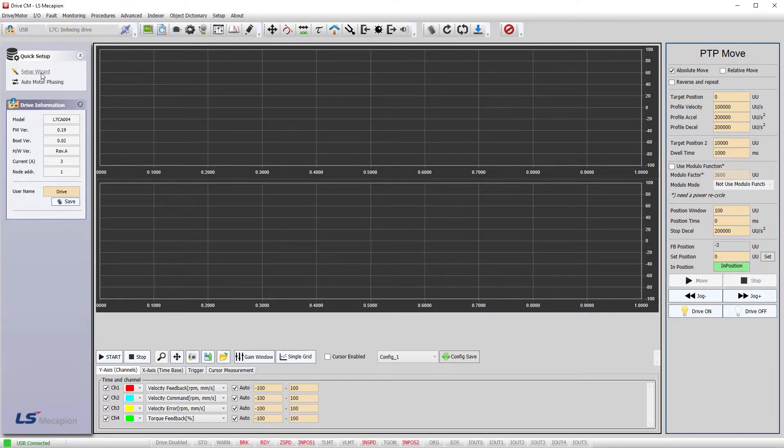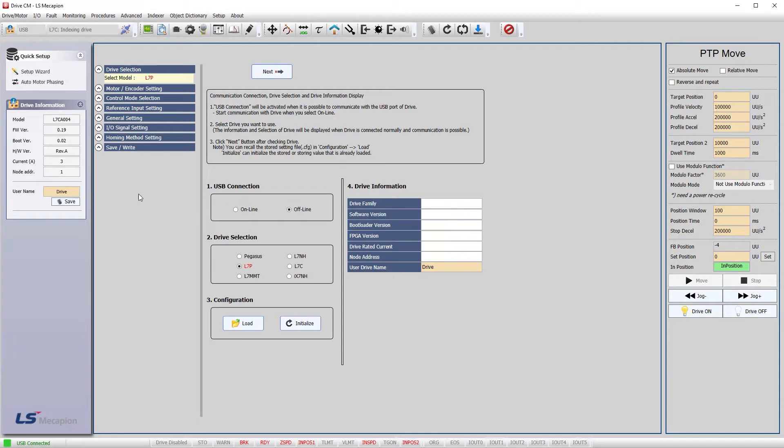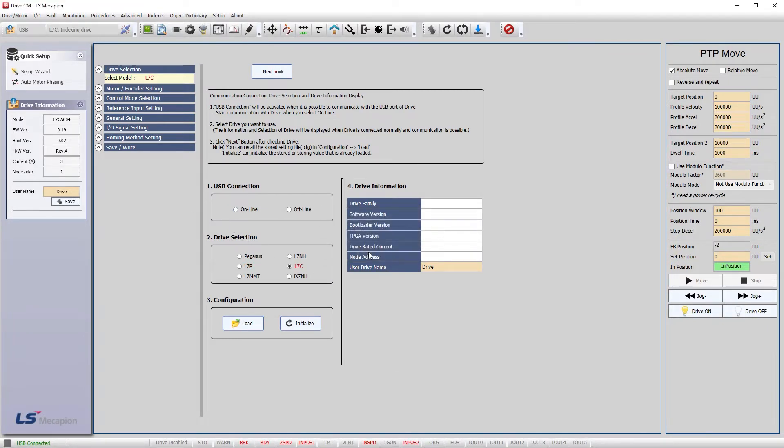Bring up the setup wizard. Go online. Yes, we want to read the parameters from the drive so when we write out the new ones we don't overwrite the drive with whatever this configuration software default values were.